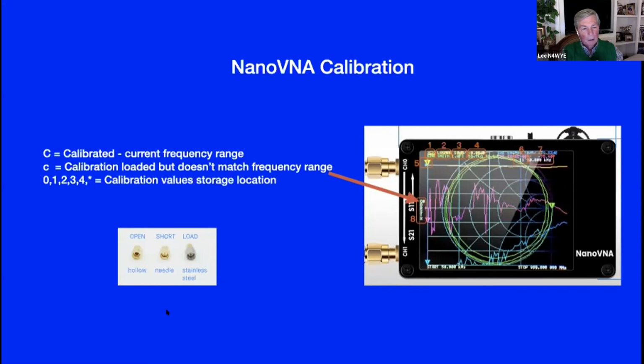And down here is the open, which is a hollow SMA connector, a short, and then a 50 ohm load. And those are the loads that you put on this port as you go through the calibration procedure. I'm not going to go through that detail here in this presentation. There's just not enough time, but it's a fairly straightforward thing. Basically, you set it up for calibration. You put the open on there. You hit the open on the menu. It goes to short. You put the short on there. You hit the load on the menu, and it just goes down and ripples through, and you're done. There's no adjustments that you have to make. The unit is self-calibrating as it goes through.